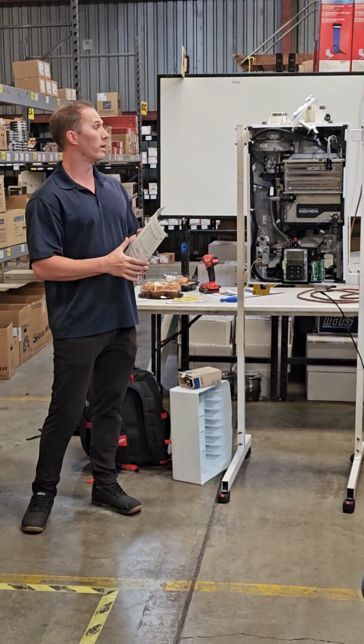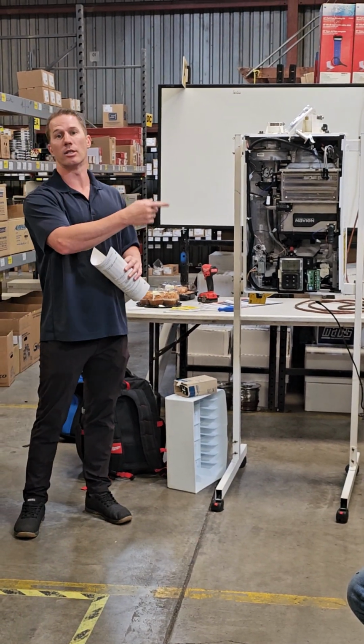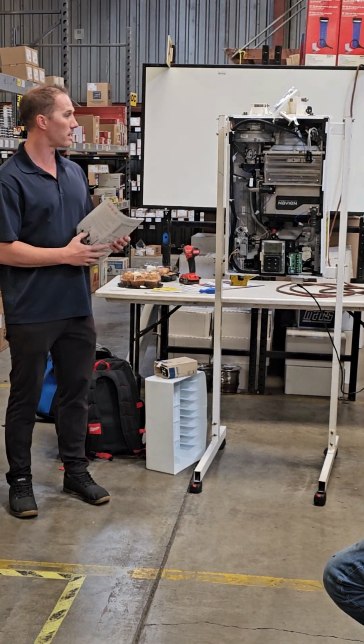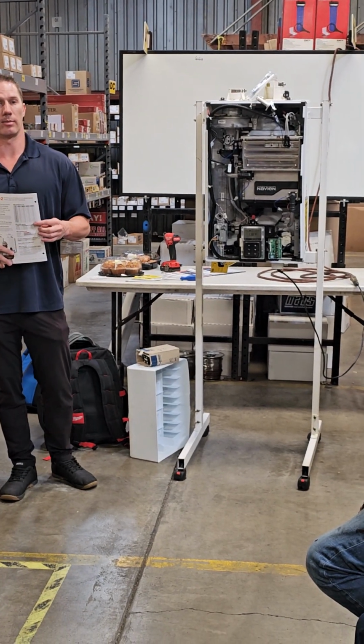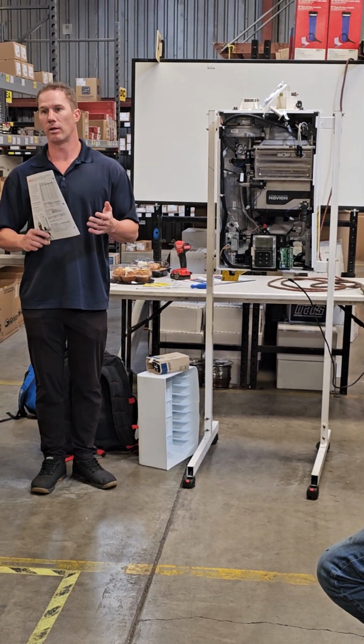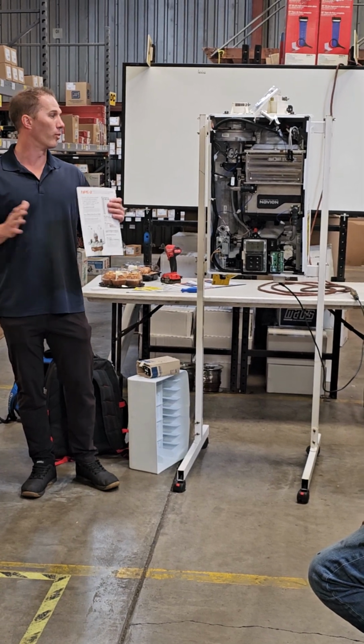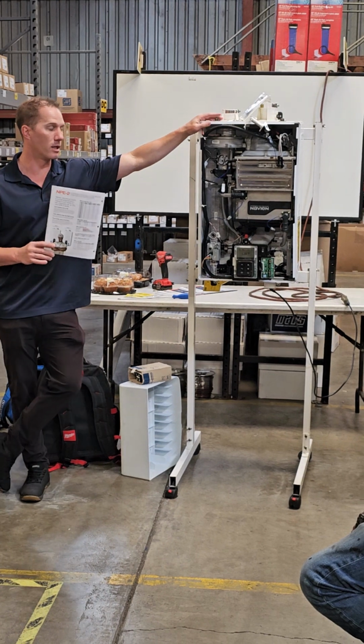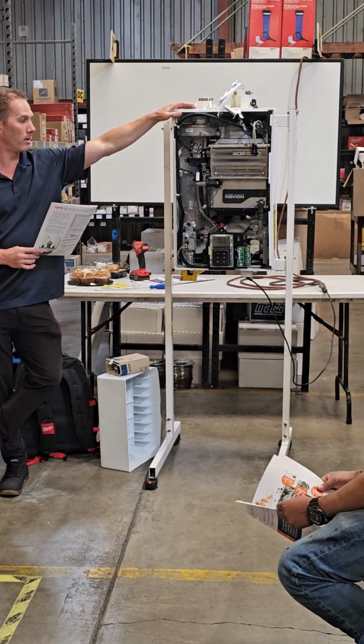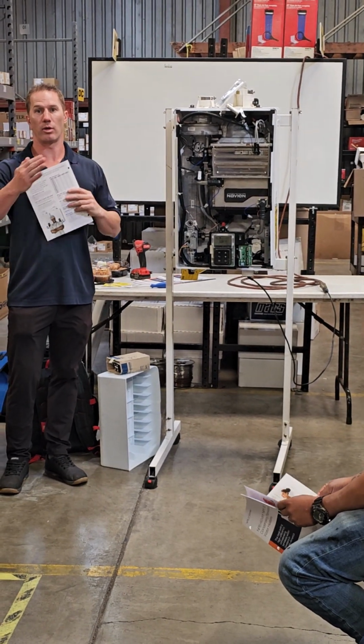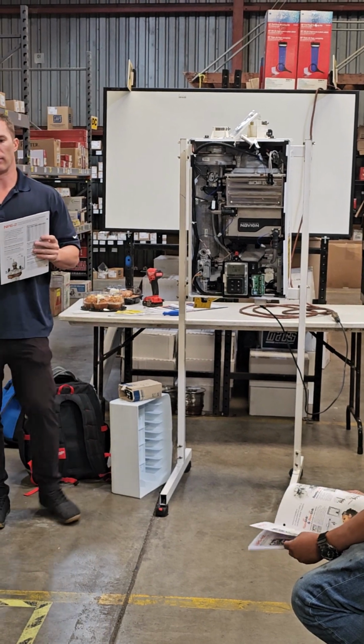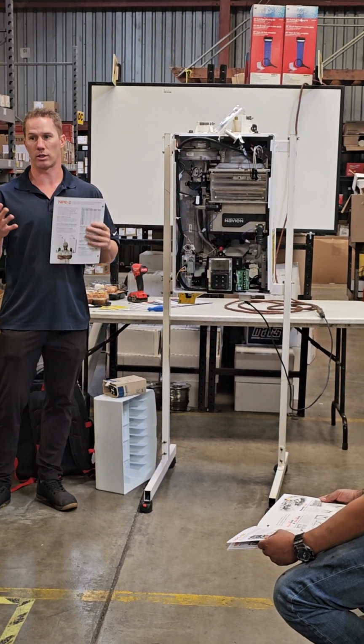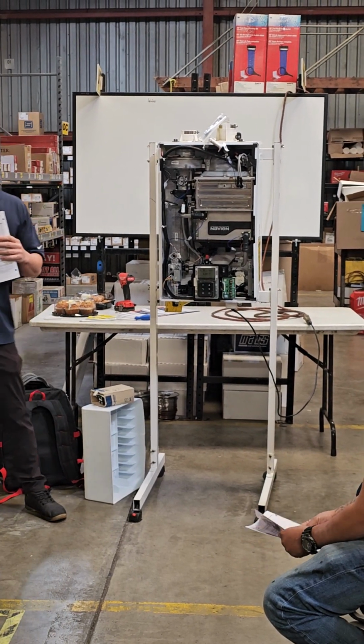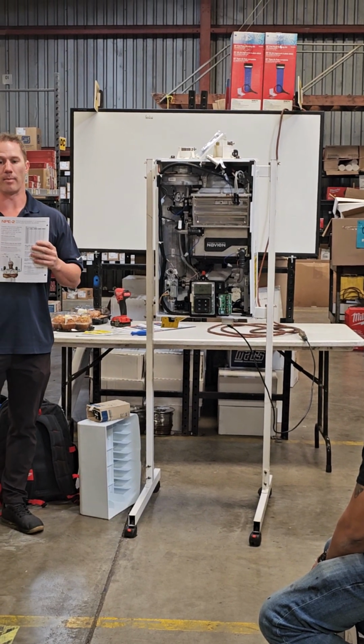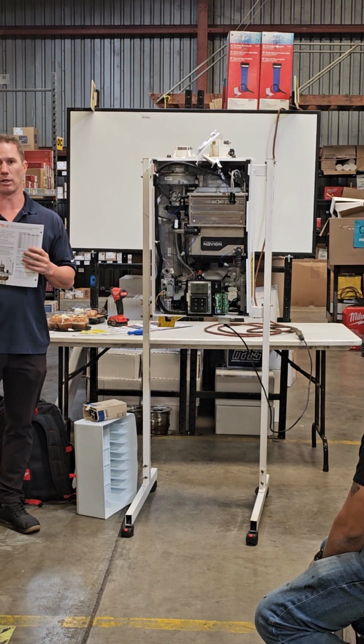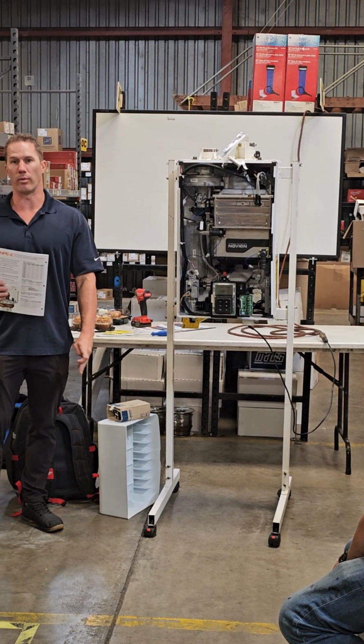When you're talking about hooking up a commercial dishwasher and cascading 2, 3, 4 units together, these things are set up a certain way. I worked with some guys down in Sacramento for a restaurant, and we put 6 units cascaded together. The way the tankless water heaters work when multiple are put together is that whenever there's a call for water, half of them turn on and start producing water right away. So with 6 units together, whenever there's a call, 3 units would kick on and start producing water right away, because it might be a 10 GPM dishwasher calling for a big load of hot water right away, and then it scales back.